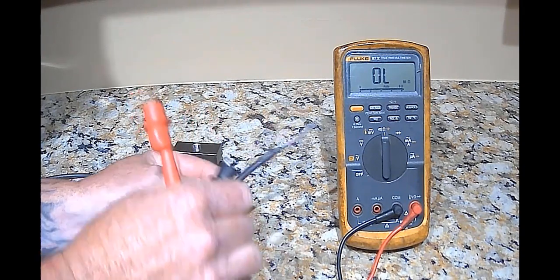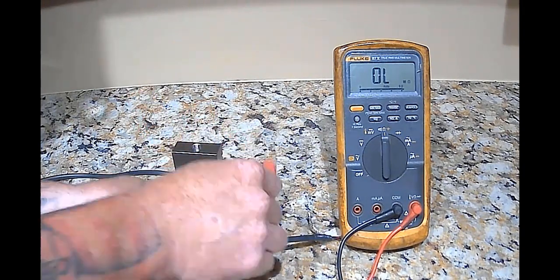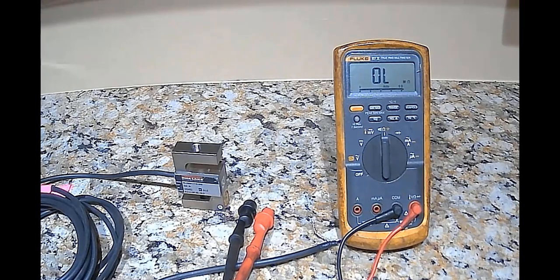The insulation resistance should match the value in the product's load cell data sheet. A lower value shows an electrical leakage caused by moisture or contamination. A very low value indicates a short circuit giving unstable load cell outputs.